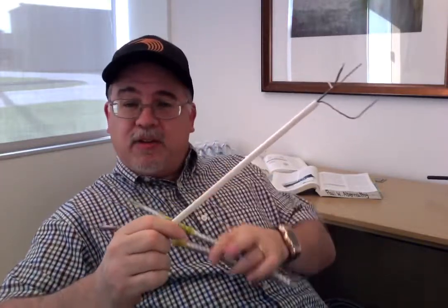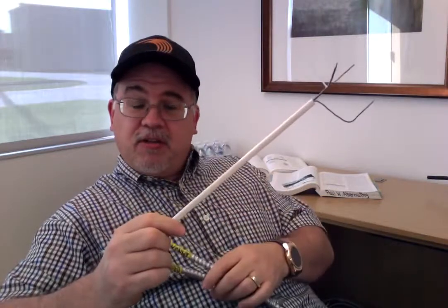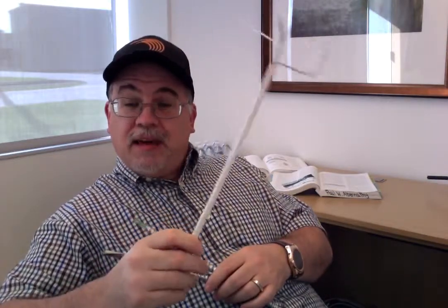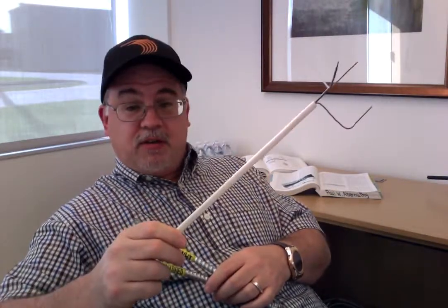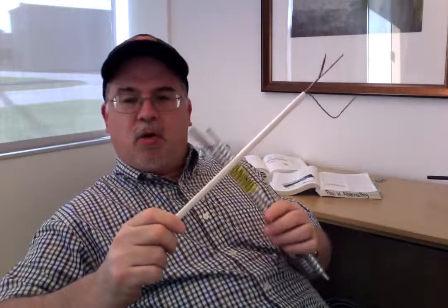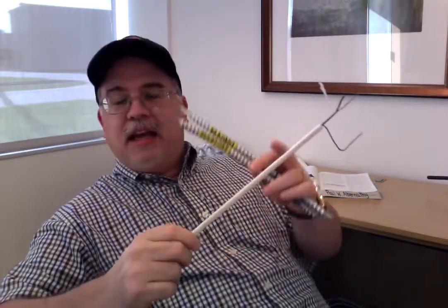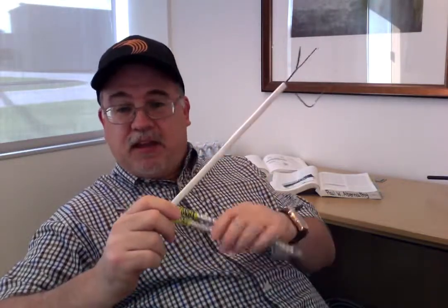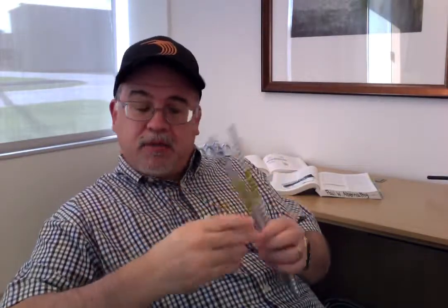The white is going to signify 14 gauge conductors, but you might see this in yellow, and that would signify 12 gauge conductors. You'll also see this available in orange. That tells you there are 10 gauge conductors inside. And of course, next size is 8 gauge, and that would be black sheathing on that. So we kind of carried that through with the MC products. So the yellow signifies that there are 12 gauge conductors in there.